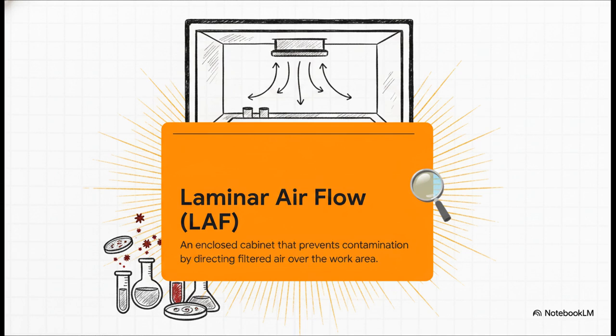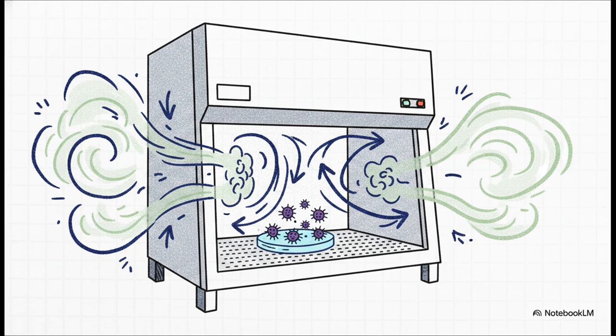It's an enclosed cabinet specifically designed to direct highly filtered, pristine air over the work area, making absolutely sure that biological samples remain perfectly uncontaminated while they're being tested. But, and this is a big but, operating a horizontal or vertical LAF hood without a fitted door causes a total cascading failure of the whole system. Without that door, unfiltered external air just rushes in. It completely disrupts the laminar flow, creating turbulence, and pulls in all this external dust and microbes. It completely ruins the sterility of the sample, and worse, it exposes the user to dangerous biohazards and escaping chemical vapors.